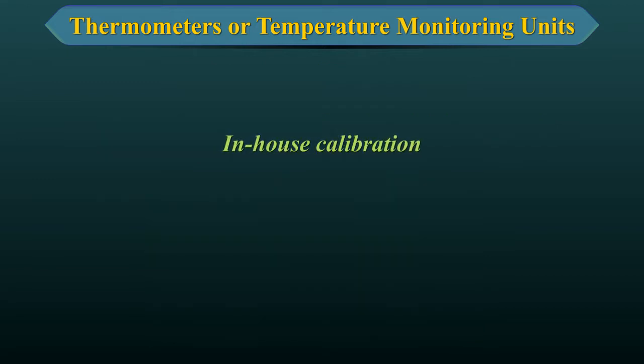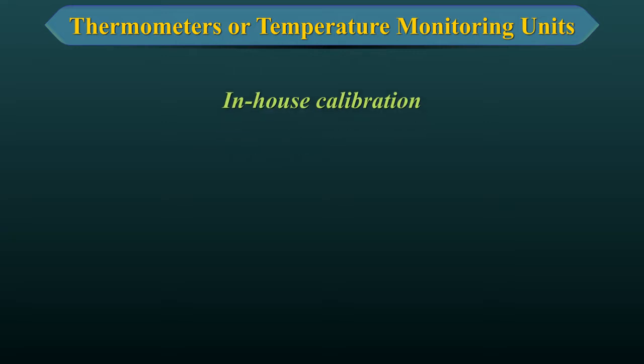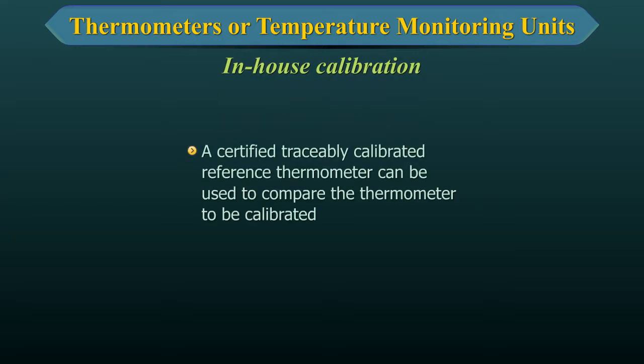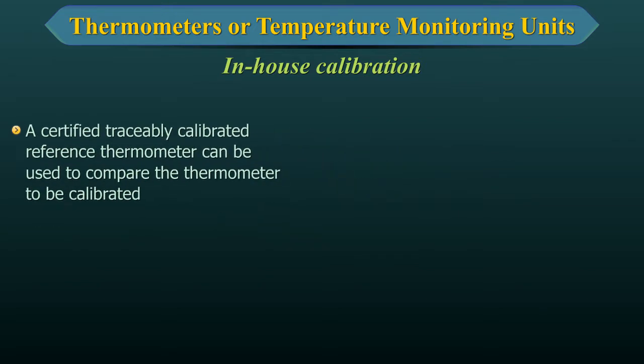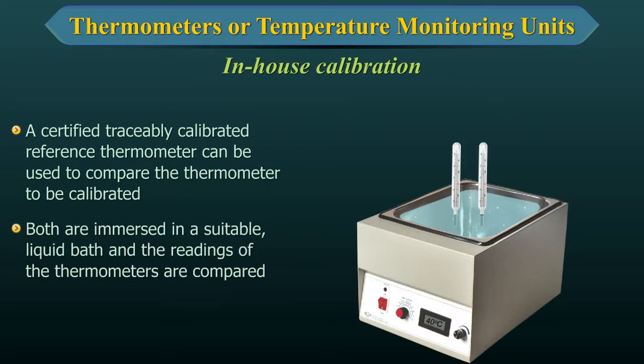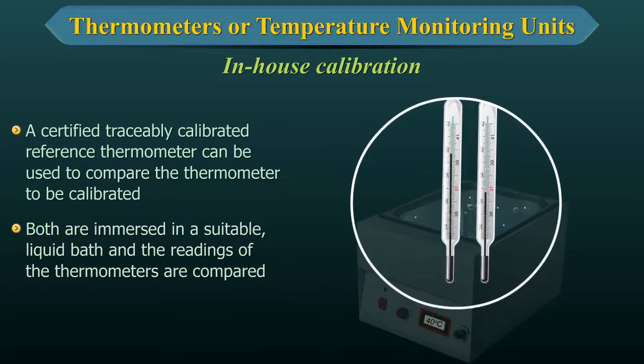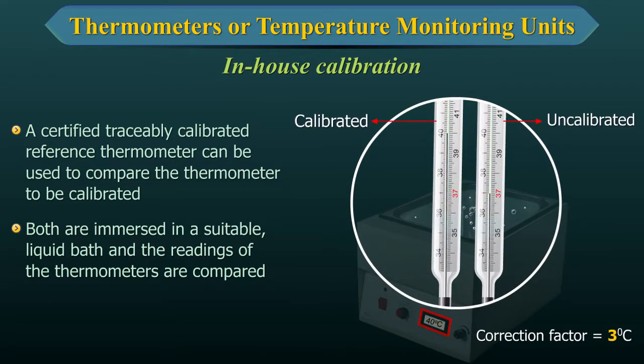In-house Calibration. A certified traceably calibrated reference thermometer can be used to compare the thermometer to be calibrated. Both are immersed in a suitable liquid bath and the readings of the thermometers are compared. The calibration temperatures should cover the range which is used in the temperature measurement.